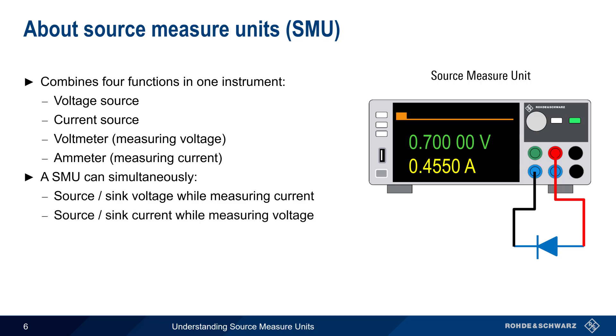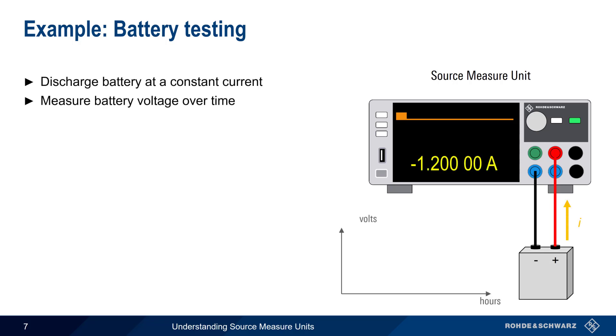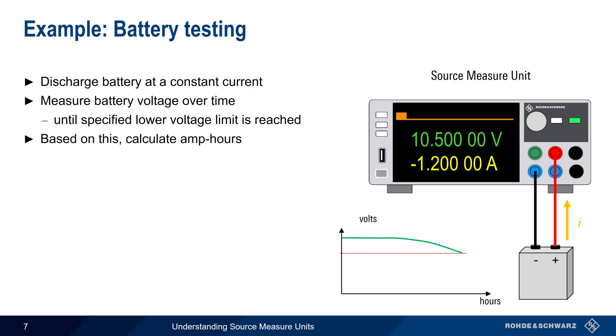Conversely, a source measure unit can source or sink current while measuring voltage. An example of using an SMU to sink current while measuring voltage is battery testing. Batteries are often tested by discharging them at a constant current and then measuring their voltage over time, usually until a specified lower voltage limit is reached. Based on this information, we can then calculate the capacity of the battery in amp hours. Amp hours is simply the number of hours needed to reach this lower voltage threshold times the constant amps drawn over this time period.